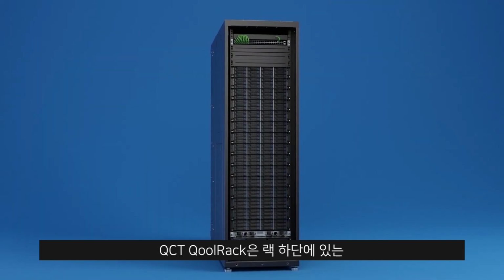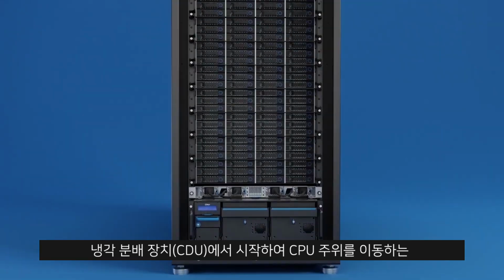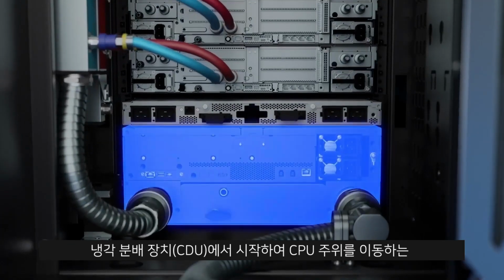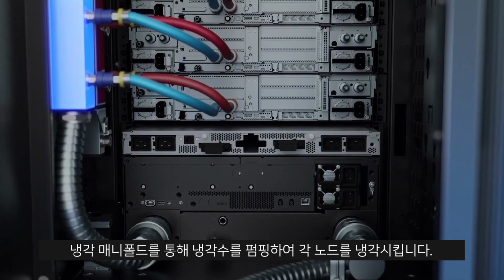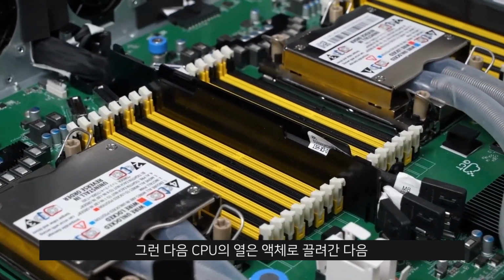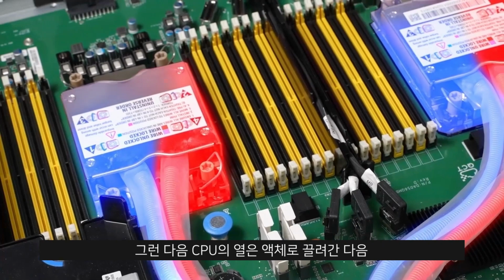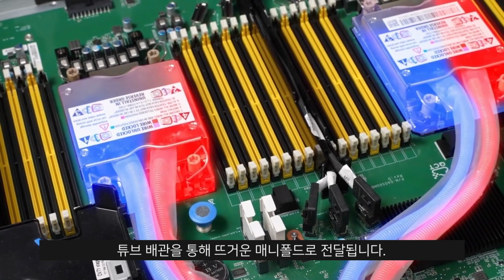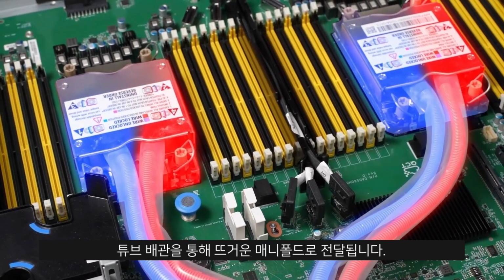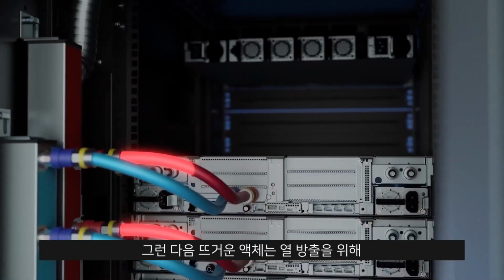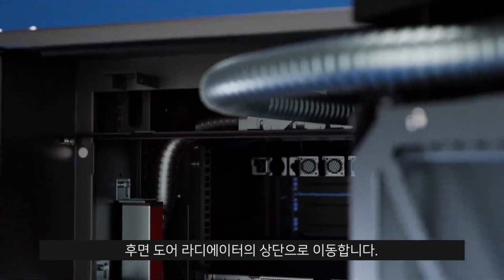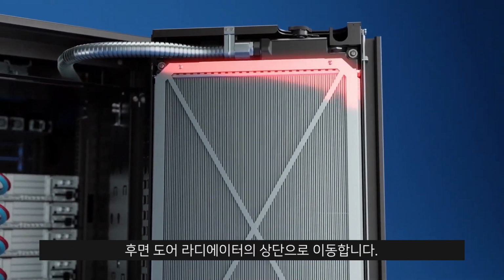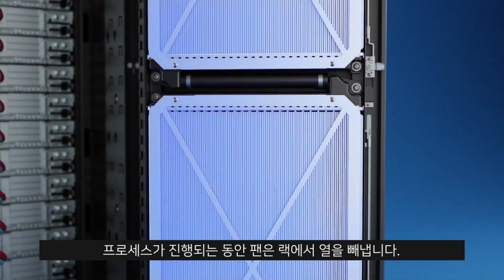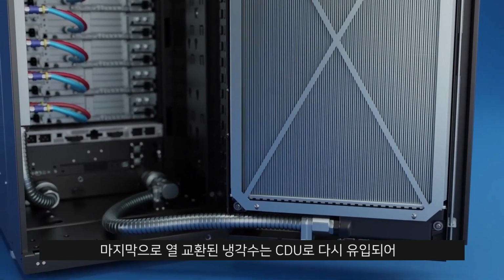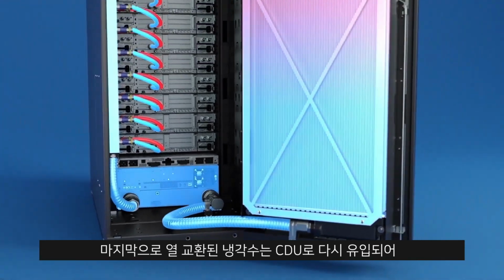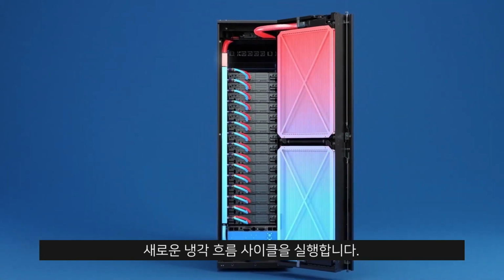QCT QoolRack starts at the cooling distribution unit, or CDU, at the bottom of the rack, which pumps coolant liquid up through the cold manifold, which travels around the CPU to cool down each node. The heat from the CPU is then drawn to the liquid, which then passes through tube piping to the hot manifold. The hot liquid then travels to the top of the rear door radiators for heat dissipation. During the process, fans would draw heat out of the rack. Finally, the heat-exchanged, cooled-down coolant will then enter back into the CDU to run a new cooling flow cycle.